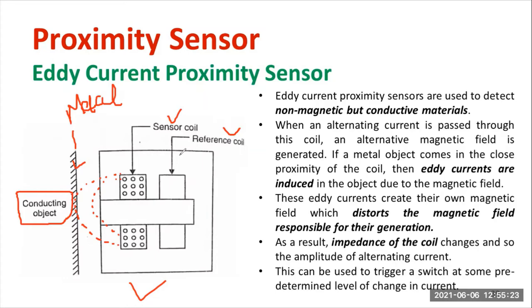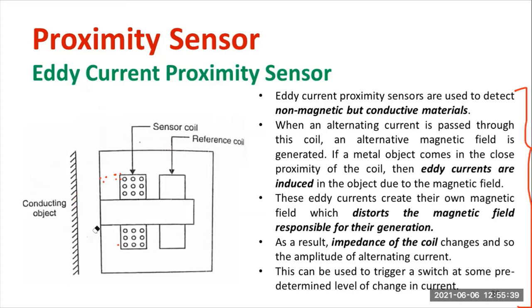A detailed explanation has been written regarding how the eddy current proximity sensor operates. In conclusion, the ultimate goal is to detect the presence of a metal object. Current continuously passes through the coil, magnetic field is produced, it interacts with the conductive object, inducing an EMF, which generates eddy current. The eddy current distorts the field produced by the coil, resulting in changes in impedance. This impedance change is connected to a switch or actuator such as an alarm, which activates to identify that an object is nearby.